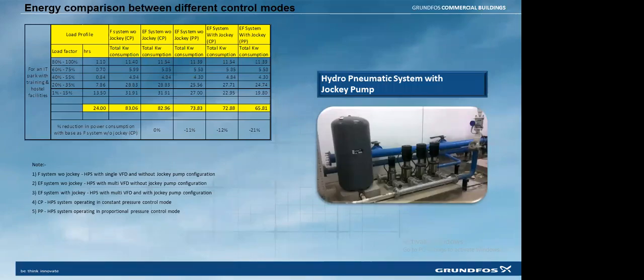We made an energy analysis for the pilot pump arrangement, comparing our existing single VFD arrangement, a system with multiple VFD, multiple VFD with a jockey pump arrangement, and multiple VFD including our proportional pressure control. How much energy can be saved? Compared with our conventional single VFD hydropneumatic system, we can have on average at least 20% to 25% better energy saving. That is the conclusion we have taken from our studies.